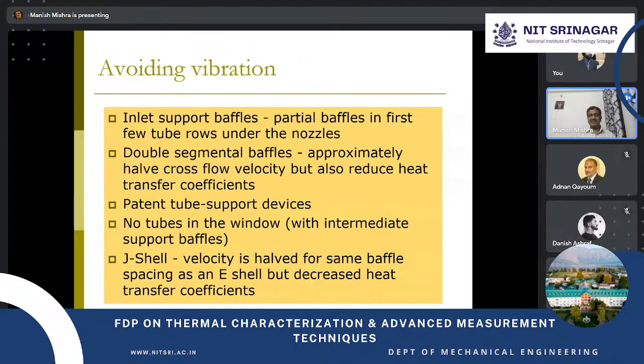For avoiding vibration, the baffle is one of the simplest solutions we have. Apart from turbulence, increasing residence time and increasing the total length of travel, it provides one of the best ways of supporting the tubes inside the shell. At the same time, it dampens the vibration also, if we select the proper baffle material. So the easiest solution is putting in the baffle, which is required otherwise also. But apart from baffling, there are other provisions by which we can reduce the vibration to some extent.